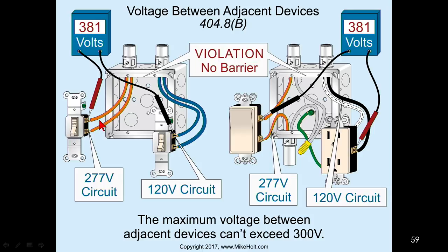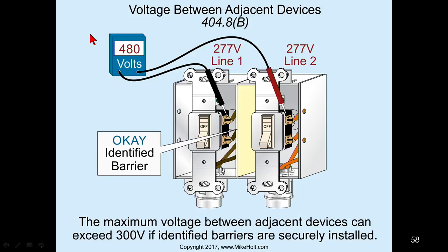What about if I have a 120 and 277? Well, the voltage between the 120 and the 277 could be as high as 381. It exceeds 300 volts. So therefore, I'd have to have a barrier here. So look at this. 120 and 120 would give you 240, you're fine. 120 and 277 gives you 381, you're not fine. 277 and 277 gives you 480, you're not fine. So whenever you have a 480 volt system, you have to have barriers between the switches.